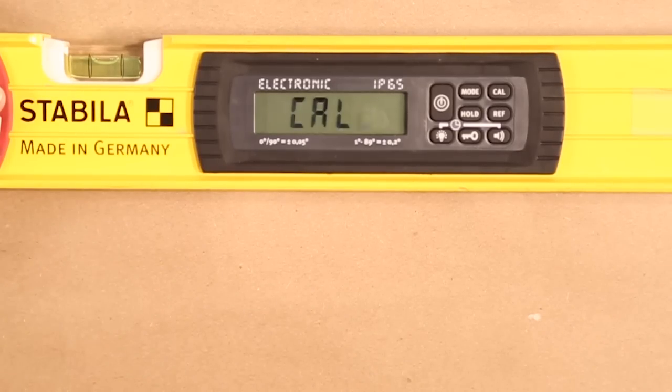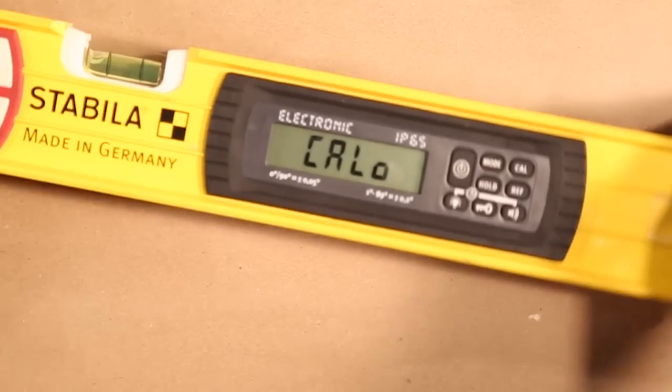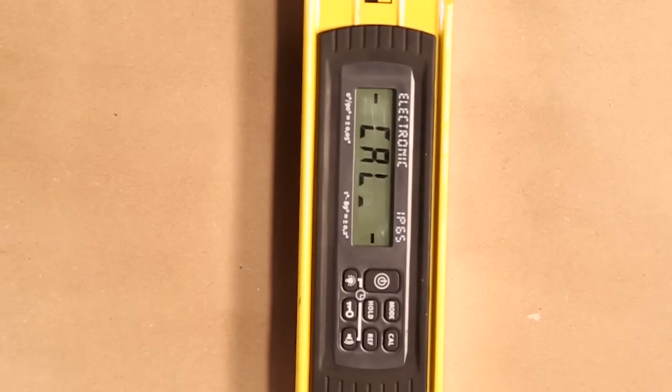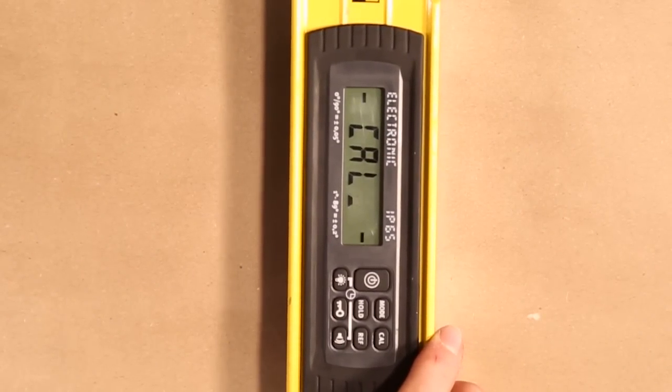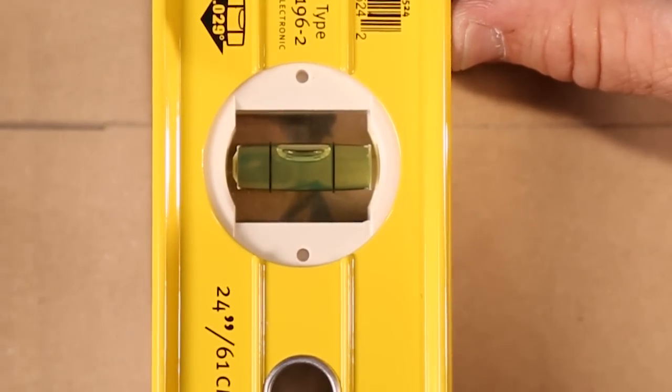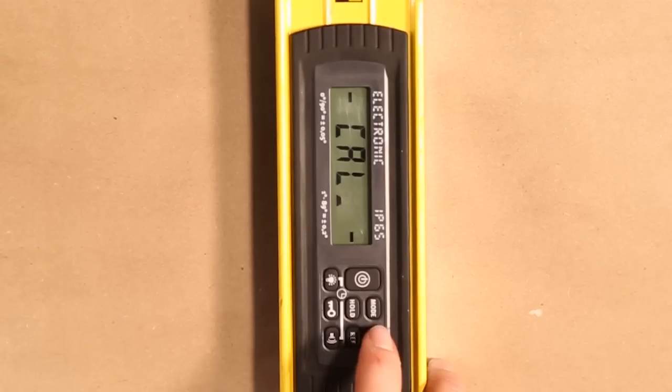You're going to notice the bottom line will stop flashing. That's when you do your first rotation. We're going to rotate counterclockwise. You're going to center your top vial. You want to get that perfect. Once that's done, you're going to hit the calibration.